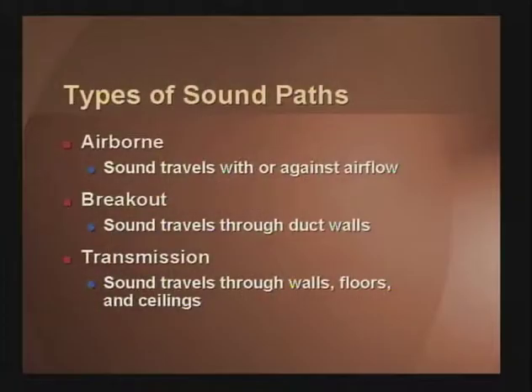Depending upon the type of equipment you have and the installation, you can have a number of different paths involved, but generally they'll fall into three different categories. The categories are airborne sound, and that's sound that travels with or against the airflow, breakout sound, sound that travels through duct walls, and transmission sound, sound that travels through floors and ceilings.